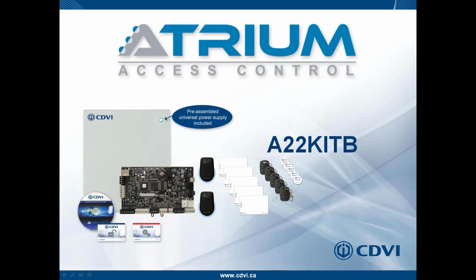Now relay 1 by default follows the lock output for lock 1. Relay 2 by default follows the lock output for lock 2. What does that mean? When I swipe a card, if I have access, the lock output will be activated to be able to unlock the door, and the relay will also activate. Now, if you're not using an external power supply, that relay is just floating free. It's doing nothing else than going on and off.